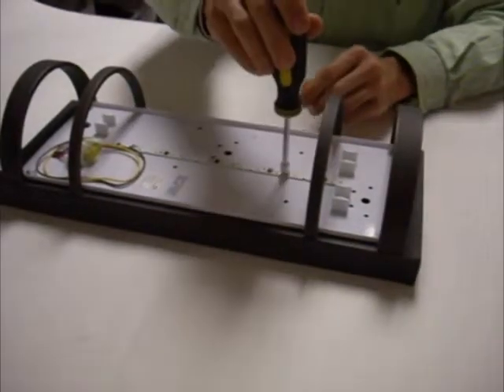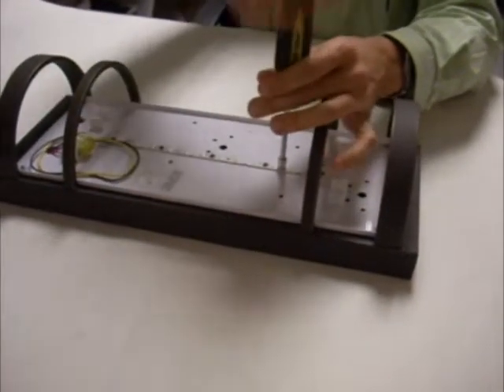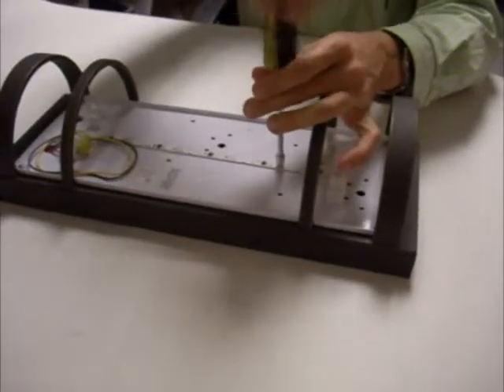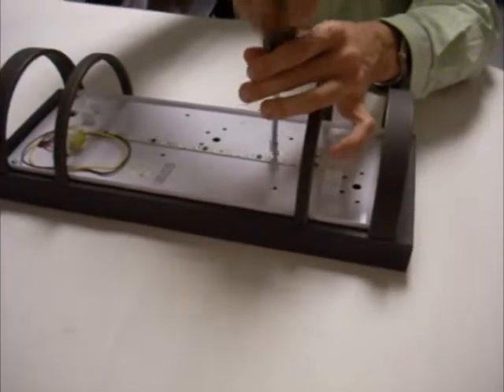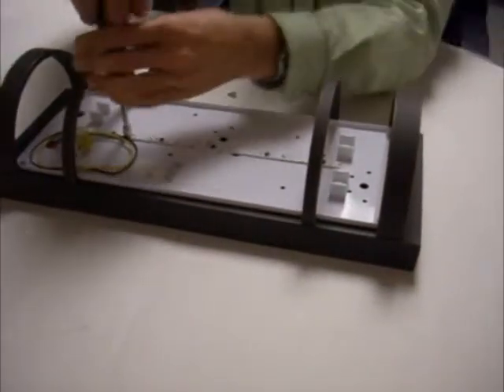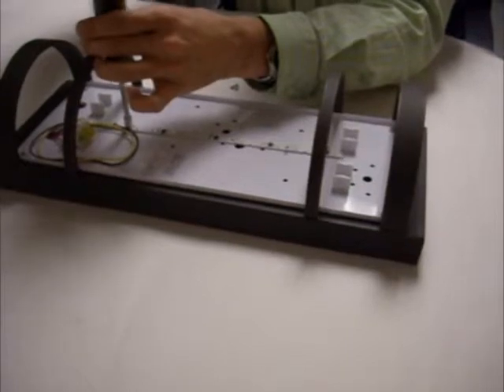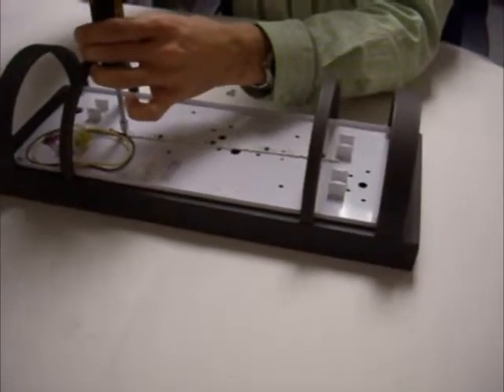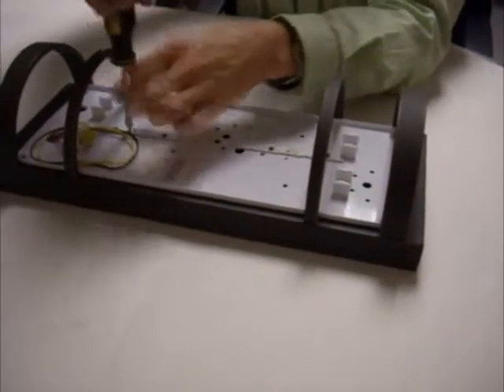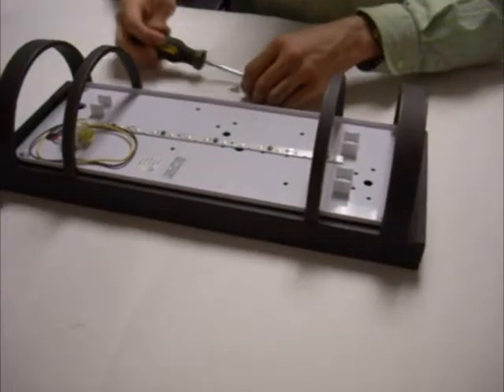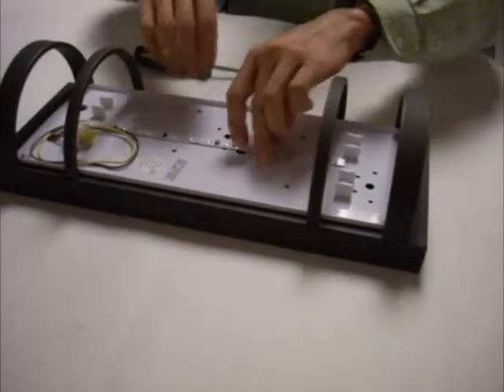Now one needs to simply unscrew the pair of fastener screws which secure the LED light engine to the panel of the fixture. Please note that there is a thermal grease on the back side of the LED fixture that facilitates heat dissipation.